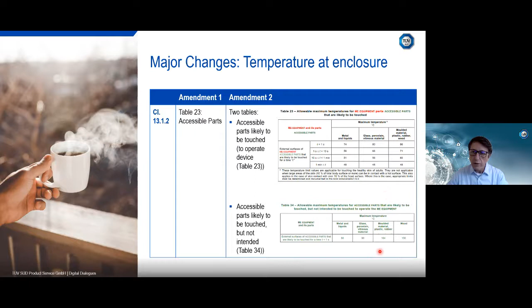Clause 13.1.2 is about temperatures. In the past, Amendment 1 had only one table talking about accessible parts. In Amendment 2, we now have two tables. The first table, 23, is about accessible parts likely to be touched, usually needed to operate the device. Table 34, in contrast, is also about accessible parts likely to be touched, but usually not intended to be touched. So we now have a difference between temperature limits. For instance, for molded material plastics, table 23 has a limit of 86 degrees C, while table 34 has a limit of 104 degrees C. This reflects reality a bit more, where we've sometimes had higher temperatures in the past, and now they are allowed for parts which are not intended to be touched.